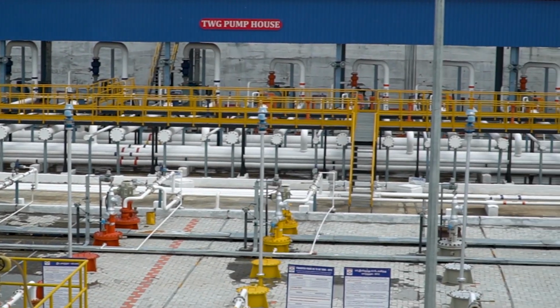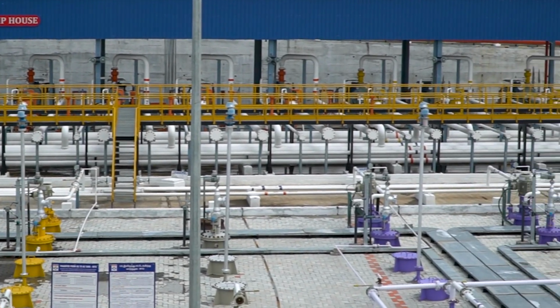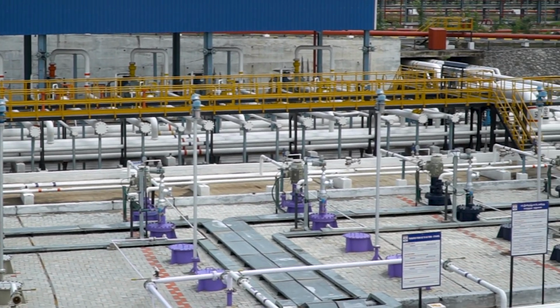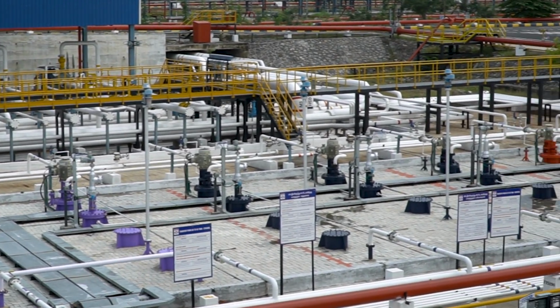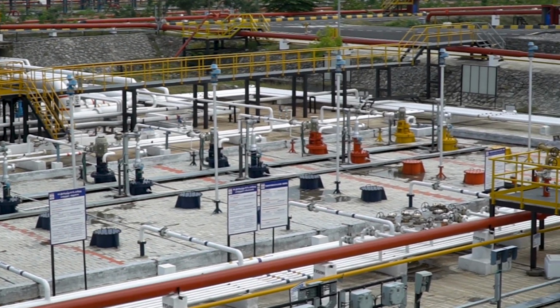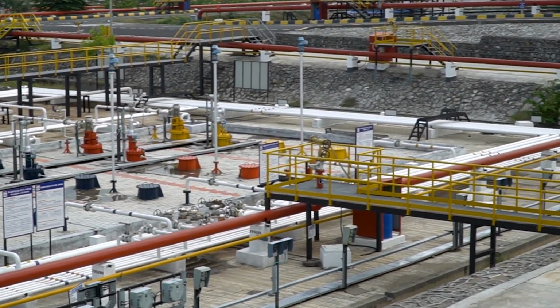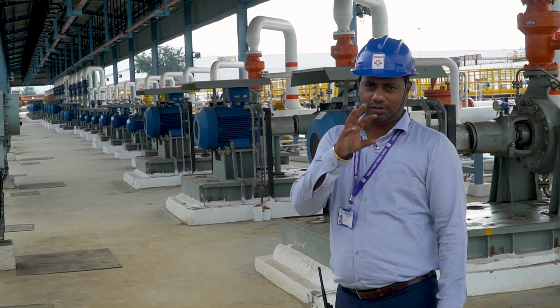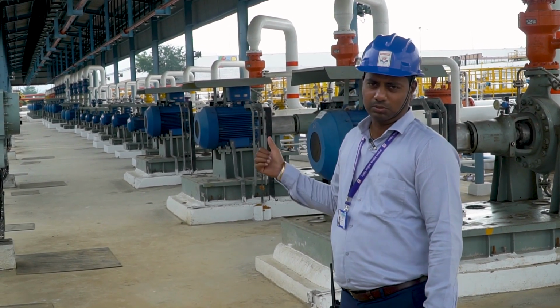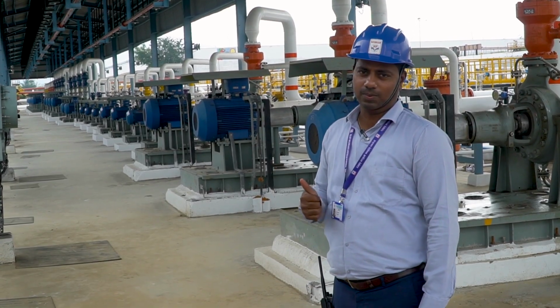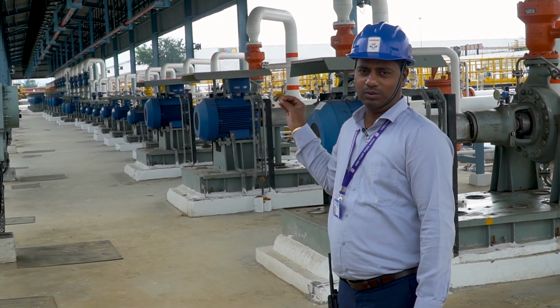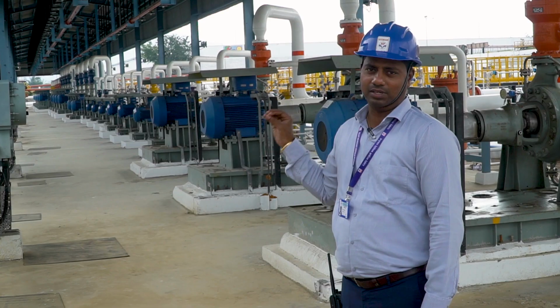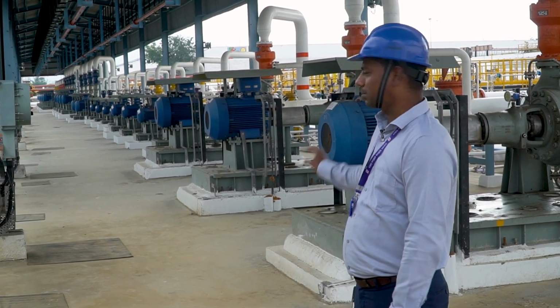Apart from this, in this area you have an underground tank. The underground tank is utilized by submersible pumps. Those submersible pumps again are connected to a motor. So whatever is applicable to these motors is applicable to the UG tank motors also. We check frequently the behavior of the motors of the underground as well as the above-ground pumps.